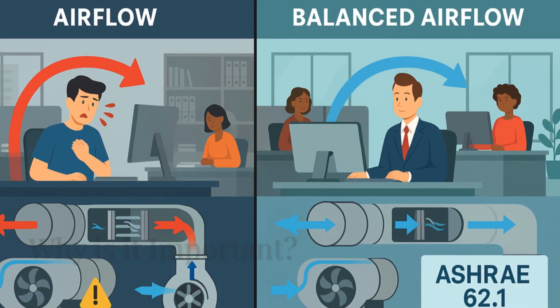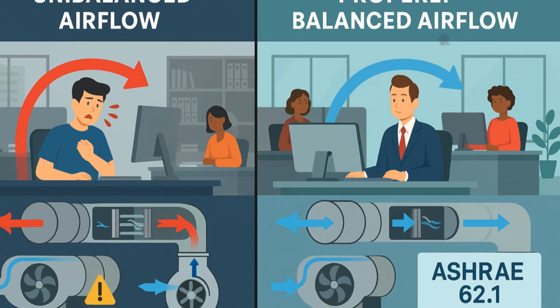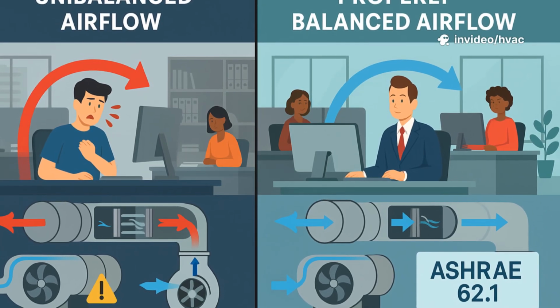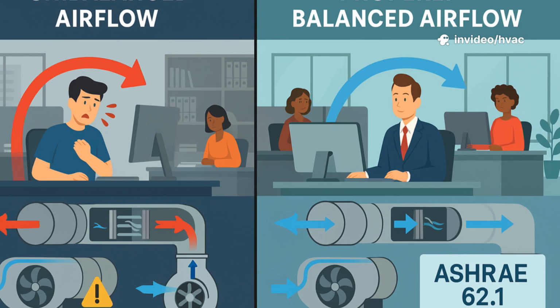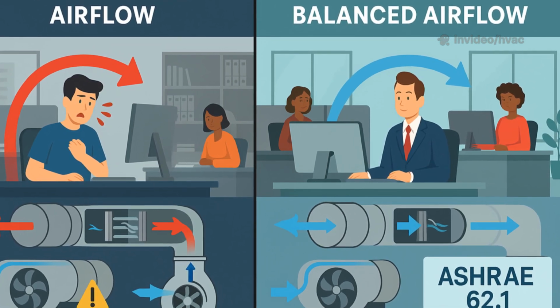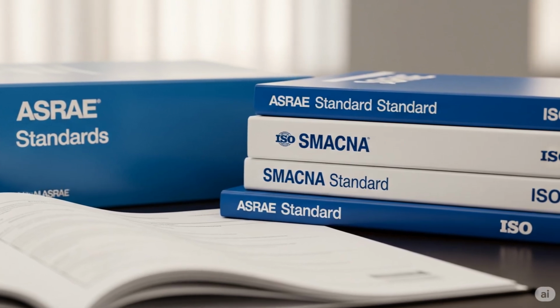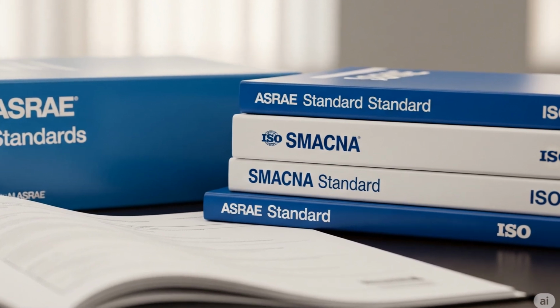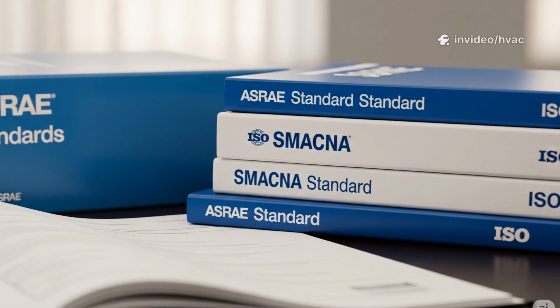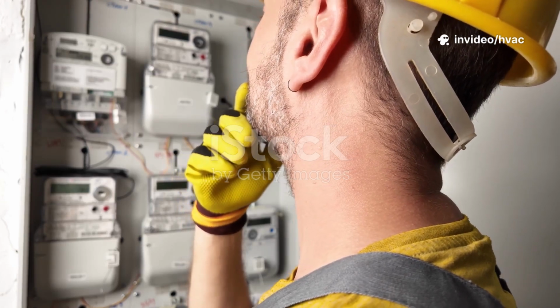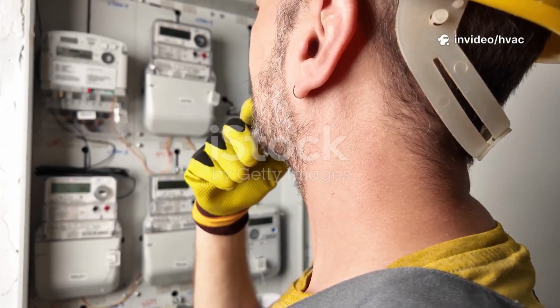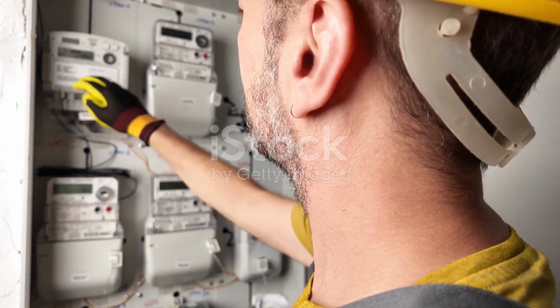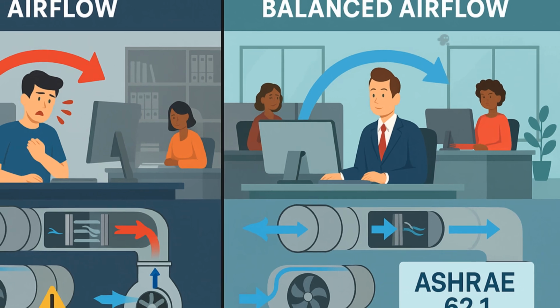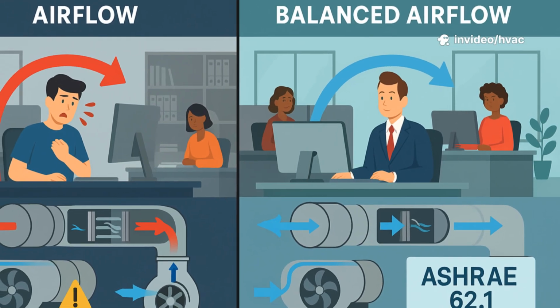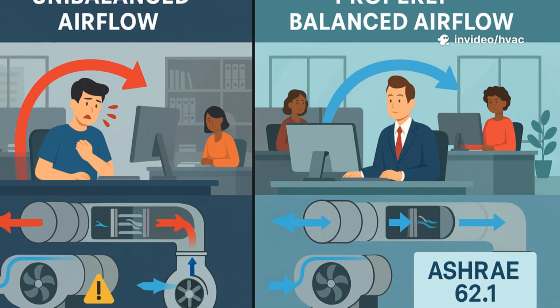If airflow isn't measured and balanced, some areas may be overventilated while others are underventilated. This leads to discomfort, poor indoor air quality, wasted energy, and can overload fans and chillers. An AFMS ensures you deliver the design airflow and comply with standards like ASHRAE 62.1 for ventilation. It also helps facility managers monitor system performance over time, making it easier to identify issues early and schedule preventive maintenance. Ultimately, proper airflow measurement supports occupant well-being, reduces operational costs, and contributes to achieving green building certifications.